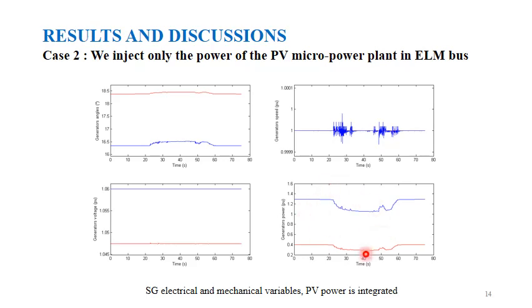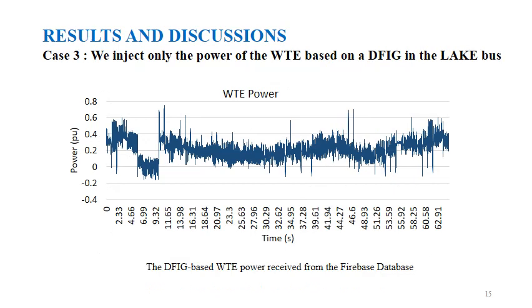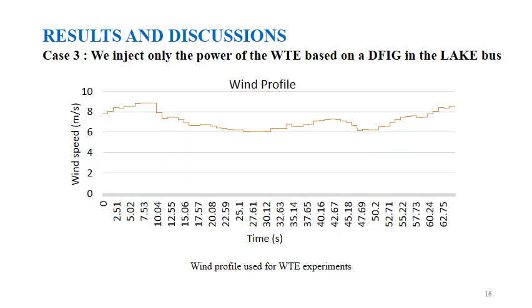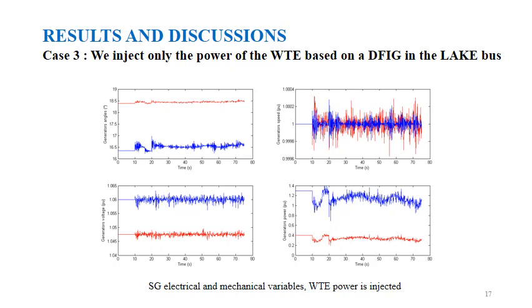The generated power from both generators adapts itself to follow the injected power. The third case is when we inject only the power of the wind turbine emulator based on a doubly-fed induction generator at the lake bus. This figure shows the variation of the injected power, which is more fluctuant compared to the injected PV power. This power is obtained under specific wind profile conditions: the wind speed must be more than 5 m/s and less than 9 m/s. In this case, the mechanical and electrical quantities are more affected by the high fluctuation of the wind turbine emulator power compared to the smoother PV power of case 2.